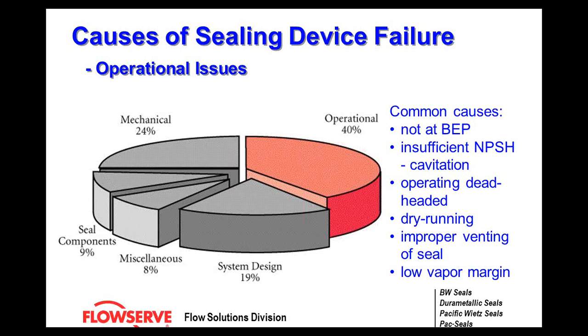Dry running can be confusing — you can have a dry run situation on the mechanical seal yet the pump was flooded. Think of a vertical pump orientation where the mechanical seal sits on top. If you don't have proper venting, an air bubble can form and won't evacuate the stuffing box chamber, causing the mechanical seal to fail through a dry run situation.